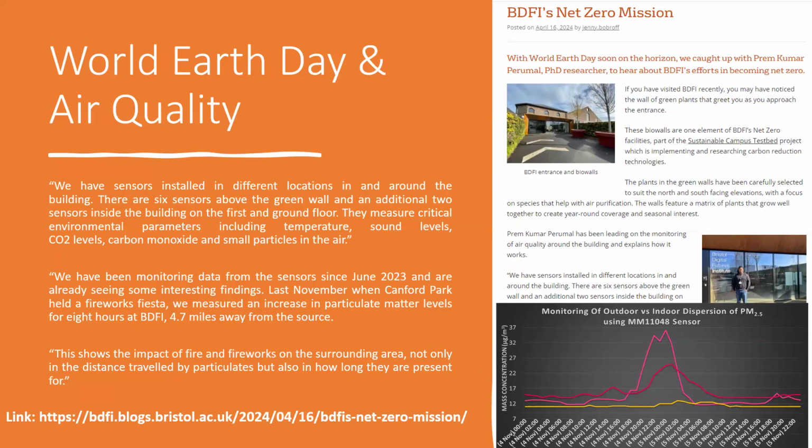And during that time the building was closed and no one was there. But you can see it takes 6 hours for it to clear. For particles inside the building, it took nearly 8 hours. So it shows the ventilation inside the building affects the clearing rate as well.